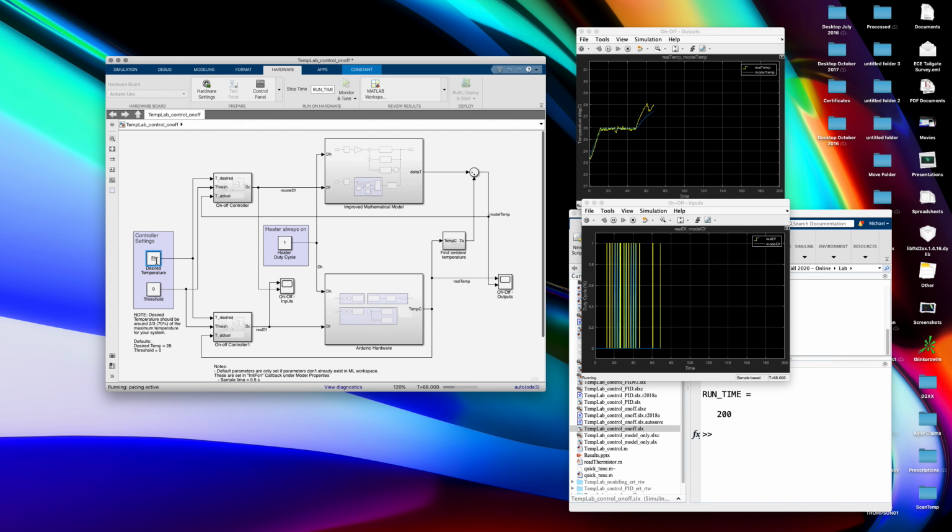All right, so I see it, as soon as it hits 28, the fan kicks on and it drives it pretty far back down. All right, and you can make that a little bigger if you wanted, but that's that one condition. And then let's see what happens when we drive it down where the fan has to kick on and off pretty quickly. So maybe around 24 degrees.